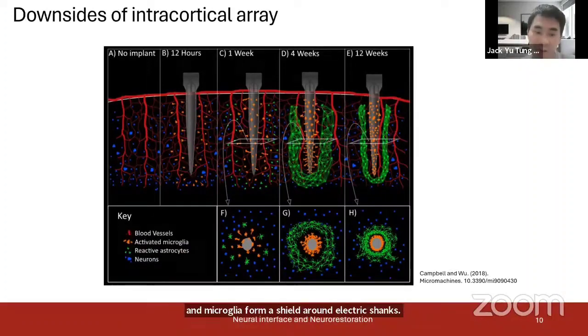insulating the neurons from the electrodes. So intracortical arrays will therefore not be very scalable, at least with the current designs, as the risk of causing injury to the neural tissue, and complications like bleeding and inflammatory reactions, are cumulative and scale with the area of coverage, limiting how wide a cortical coverage we can achieve.